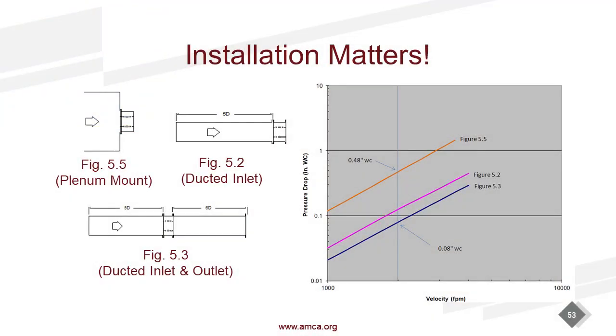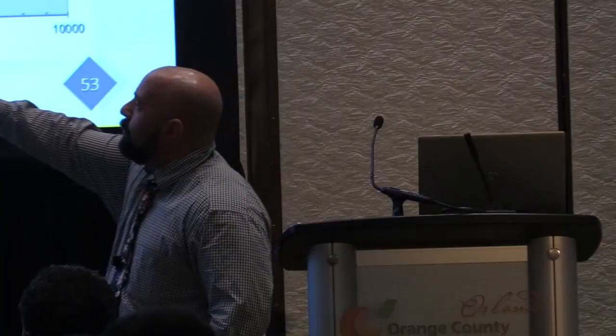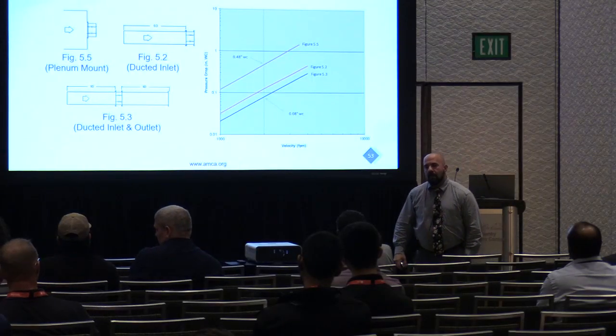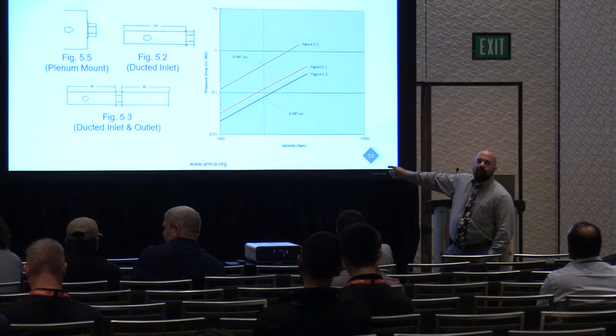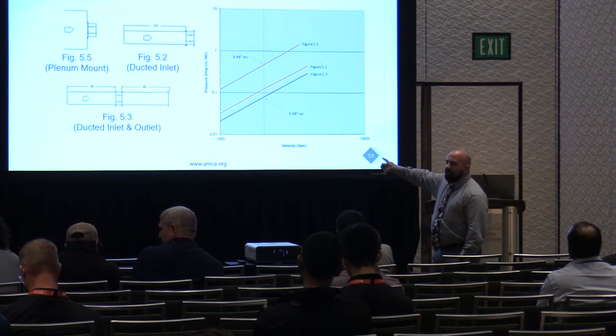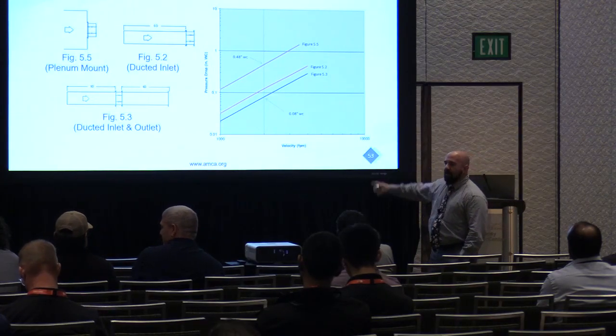So we'll keep going here. Here's why it matters. Figure 5.3, ducted in and out. It's just a sample damper. Let's call it a 12 by 12. I accidentally cut off the bottom. A 12 by 12 damper is going to run at about 0.08 inches at 1,500 feet per minute velocity. Take that same damper and put it in figure 5.5 in a plenum mount. The pressure drop went from 0.08 to 0.48. Now that's obviously for one specific damper, one specific model. This is a V-blade fire smoke damper, the most common damper specified.